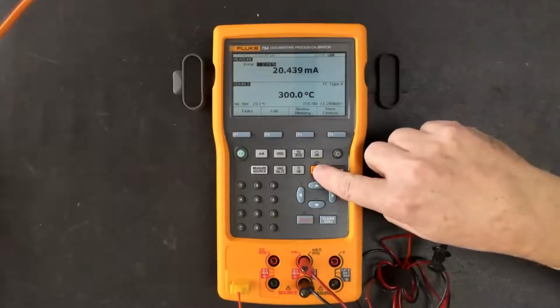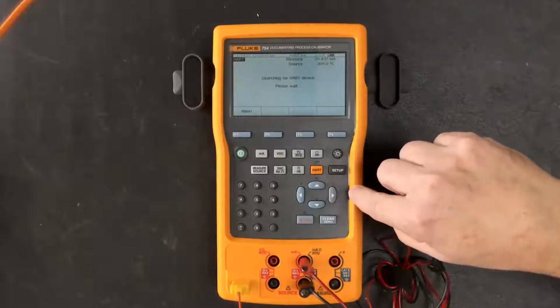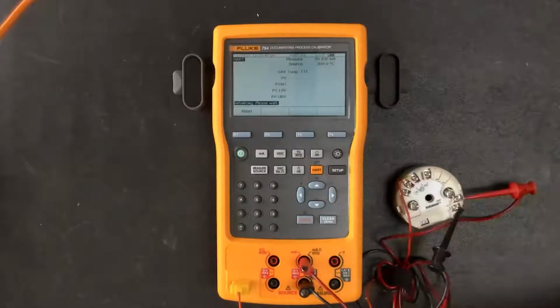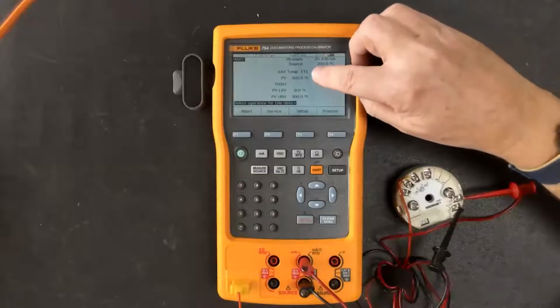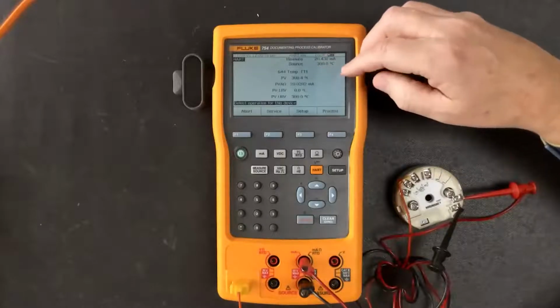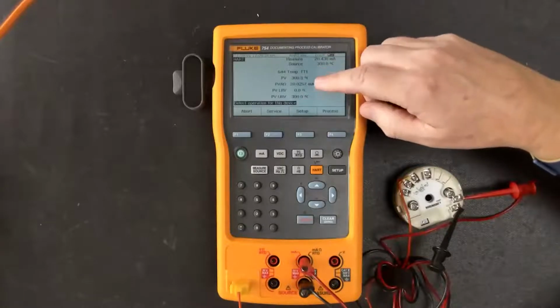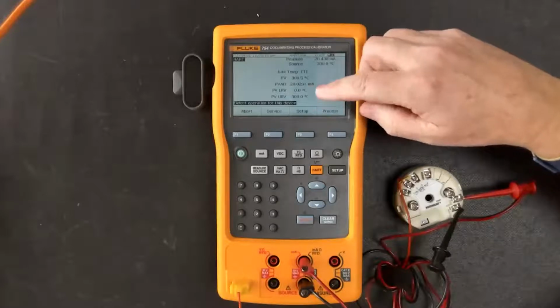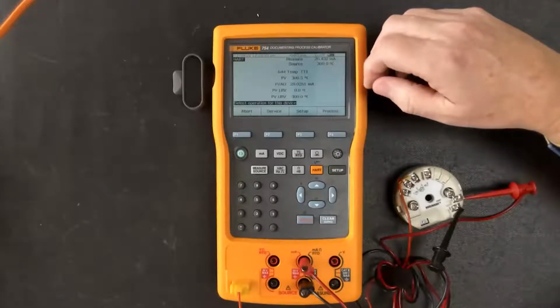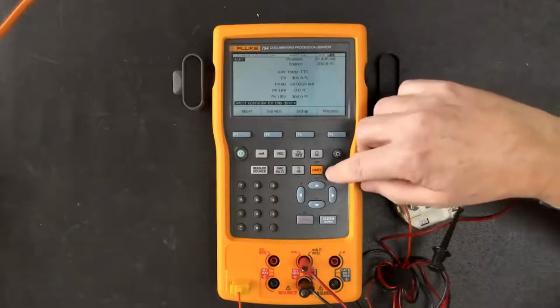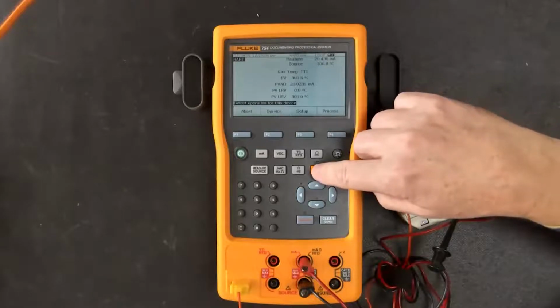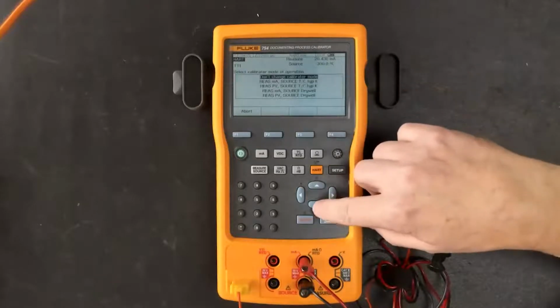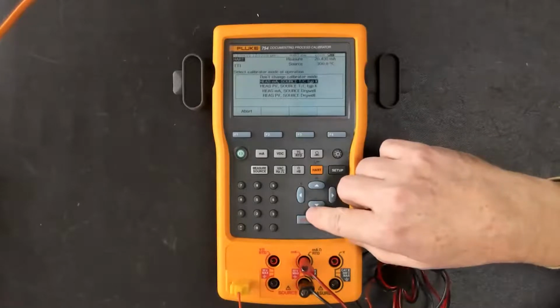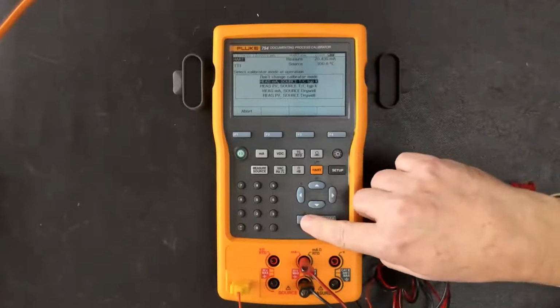If I press the HART button, we're going to go ahead and look for a HART device out there, and it finds that 644 transmitter. It's called TT1, and you can see the lower and upper range values on here. What we're going to do next is actually do a calibration. So I'm going to press the HART button again. We're going to measure milliamp, source thermocouple type K.